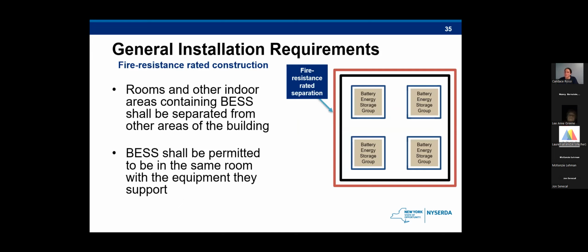Here we have the fire resistant rated construction requirement. Rooms and other indoor areas containing energy storage systems should be separated from other areas of the buildings. They shall have a 2-hour minimum fire rating for all installations. The fire protection should also include the ceiling of the room, but this is not required for walk-in containers. Also, for indoor areas, energy storage systems shall be permitted to be in the same room as the equipment they support. I think the reason for this requirement is pretty obvious, but you definitely want to ensure that if there's a fire incident, there's a high enough fire rating for the building to be evacuated to protect human health.